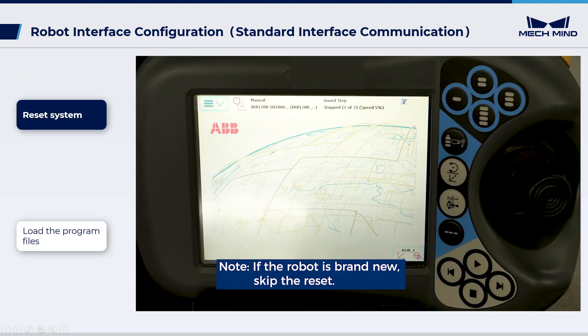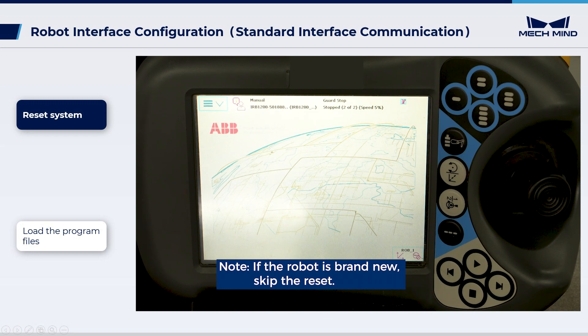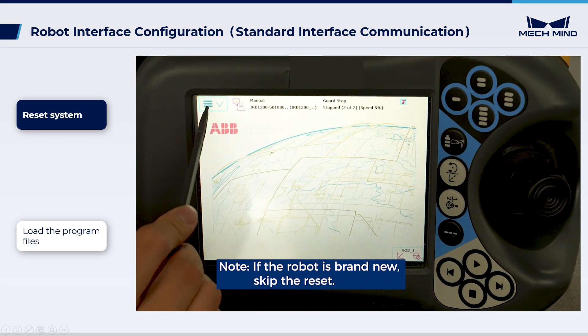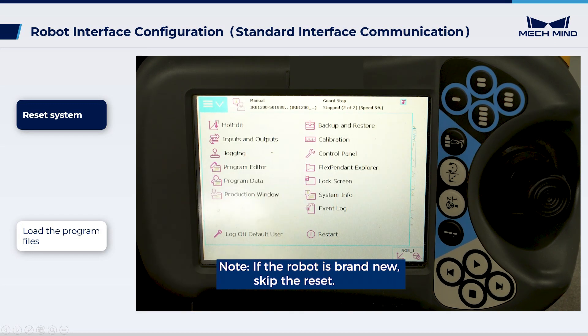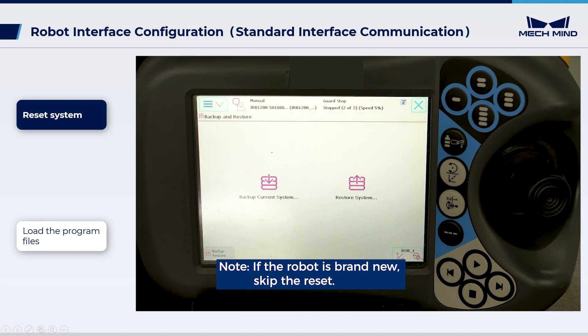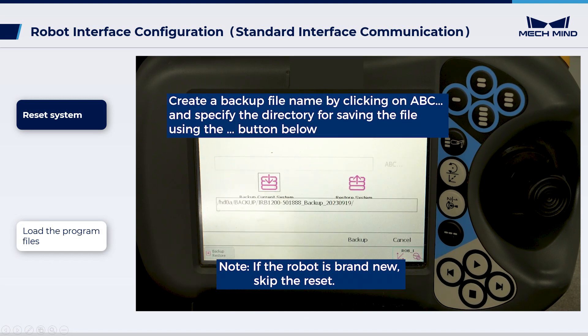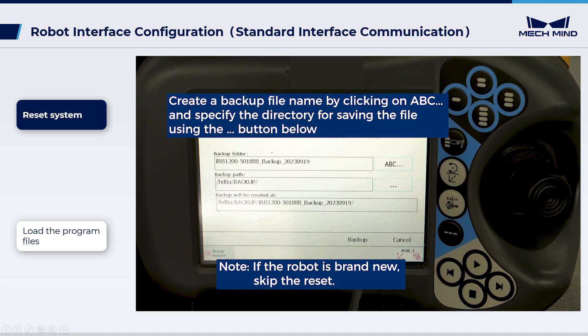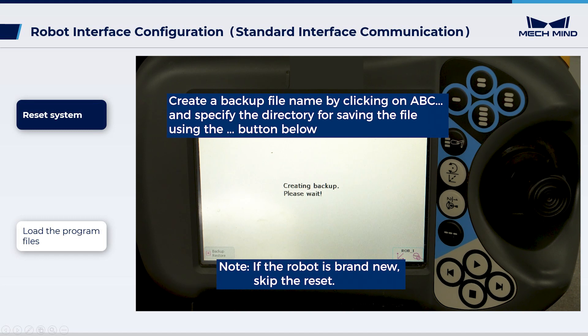Before loading program files, please back up the robot system on the teach pendant. Navigate to the home page using the menu in the upper left corner, then select Backup and Restore. Choose Backup Current System, then click Backup in the lower right to initiate the backup process.